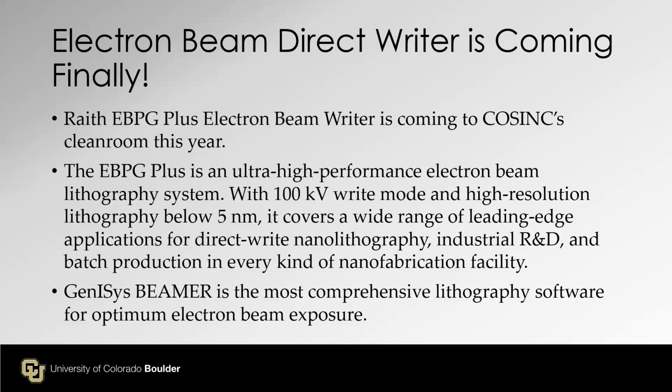Because of the high electron energy column together with all the advanced design, we can achieve resolution below 5 nanometers, which is quite impressive. Well, of course, it depends on what you want to do after you do the writing.